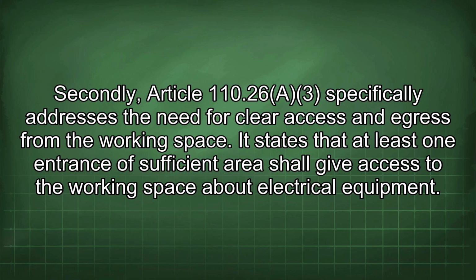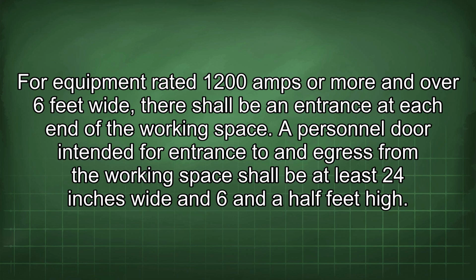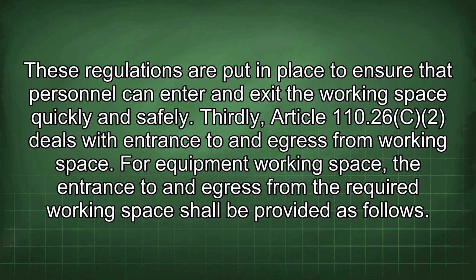Secondly, Article 110.26a specifically addresses the need for clear access and egress from the working space. It states that at least one entrance of sufficient area shall give access to the working space about electrical equipment. For equipment rated 1200 amps or more and over 6 feet wide, there shall be an entrance at each end of the working space. A personnel door intended for entrance to and egress from the working space shall be at least 24 inches wide and 6.5 feet high. These regulations are put in place to ensure that personnel can enter and exit the working space quickly and safely.